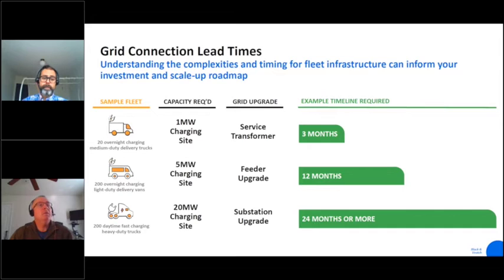To Alex's point, there are different time frames relative to getting the power you need. So what we've done is looked at some sample fleets: what the capacity would be to get there, what's the level of upgrade, and the typical timeline. For example, the smallest size fleet's potential upgrade could be a service transformer, that pole or pad mount transformer you see all the time. Typical timeline is 3 months.